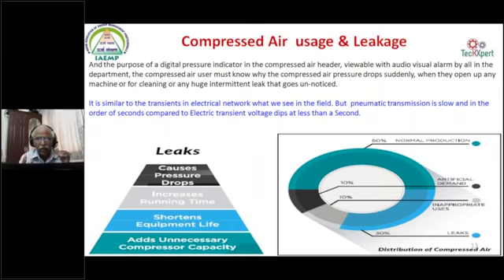By providing a buffer, instead of operating the machine at 6.8 kg, I am putting a receiver at the tail end or at the feed-forward receiver. Automatically you can bring down the pressure from 6.8 to 6.3 depending on the condition. So again, addition of receivers at the compressor house, at the tail end and at the intermediate, wherever it is located, because it doesn't consume power, but it is able to buffer the air.